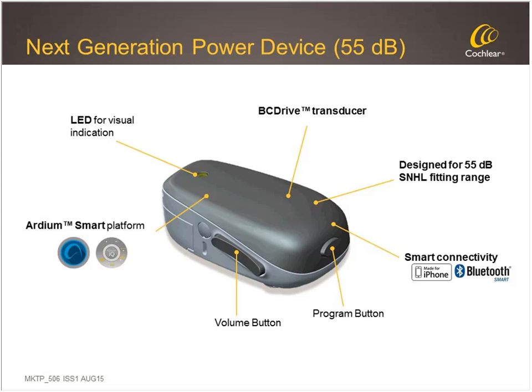And then the next one is the Baha 5 Power, and it is slightly larger than the Baha 5. You can have up to a 55 dB conductive loss with the Baha 5 Power, and it has the same BC drive transducer. It also has an LED so that you can tell if it's on or off, or if it's receiving information, and that's a little different because our Baha 5 does not have that. The Baha 5 Power also has a volume up and down, so you're able to turn the volume up and down directly on the processor. And there's also a program button, and both the Baha 5 and the Baha 5 Power have the program button.